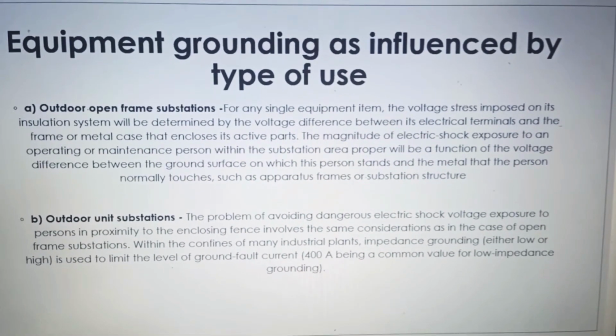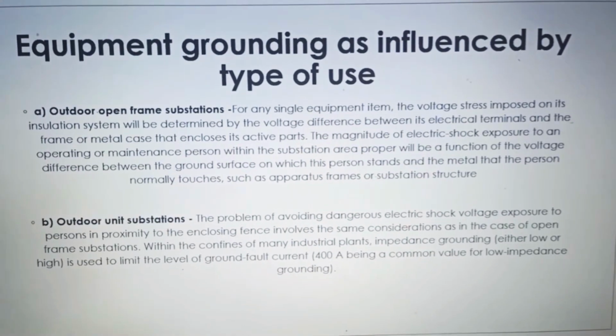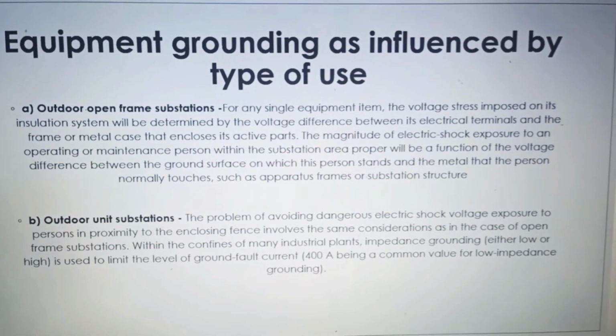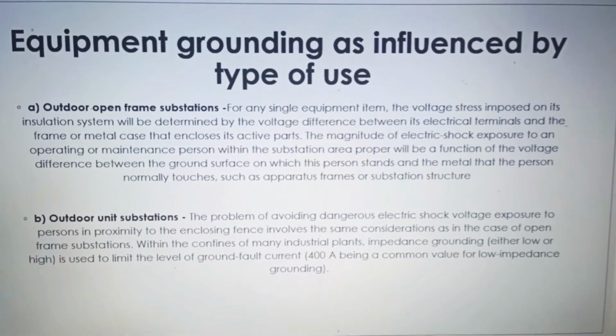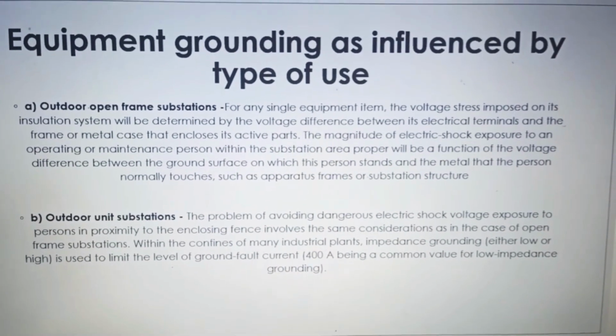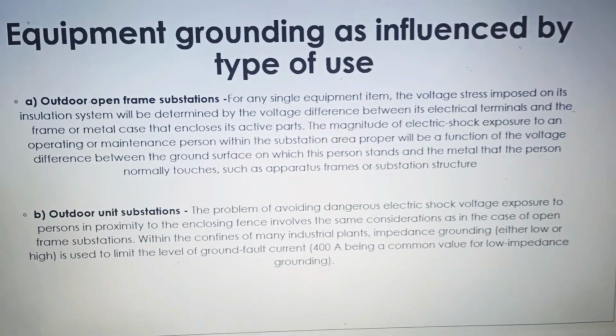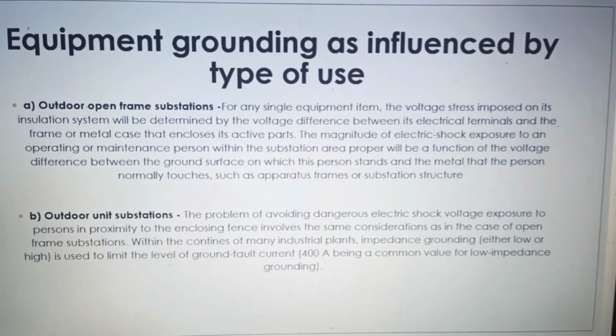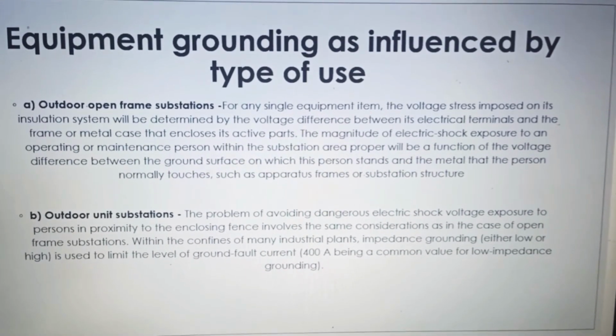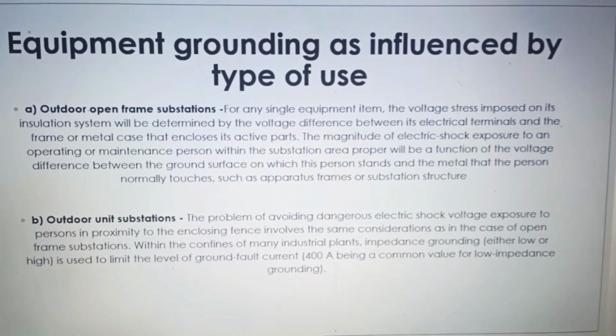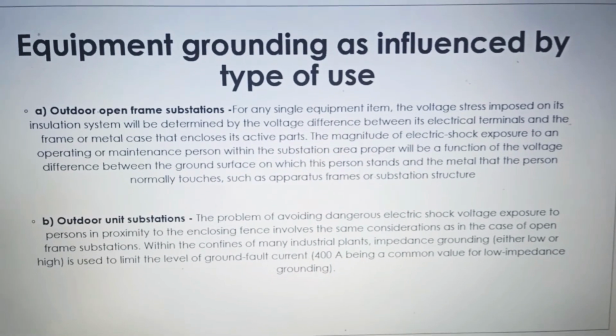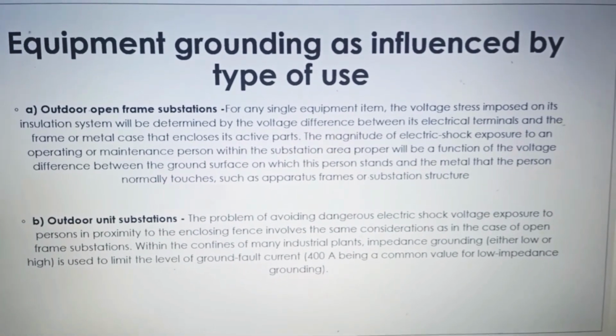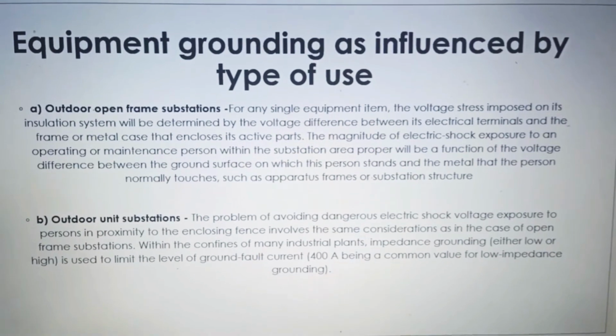Outdoor open frame substation, outdoor unit substation, outdoor portable heavy duty equipment, interior wiring system, and interior unit substation and switching center. Okay, outdoor open frame substation. The distributed nature of a typical outdoor open frame substation presents some of the most perplexing equipment grounding problems to be found anywhere.